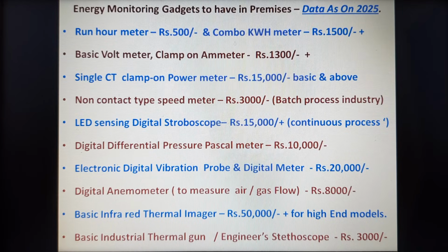So if that is above, you have to check with your OEM what corrections are to be taken in your machine. The digital anemometer measures the air or gas flow; it shows what flow is deliverable by your blowers and what is to be checked there. Not only the digital anemometer for the blowers, but for all your compressors, let us say if it is 50 HP and above, it needs a thermal mass balance principle based in situ flow meter.